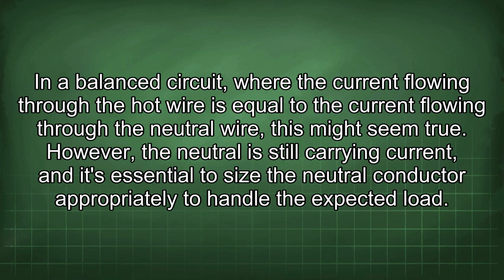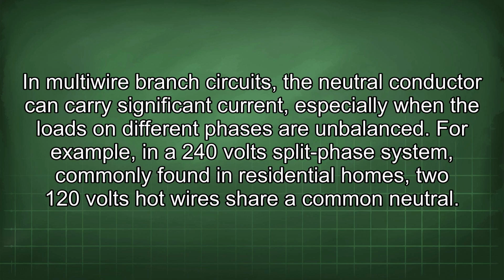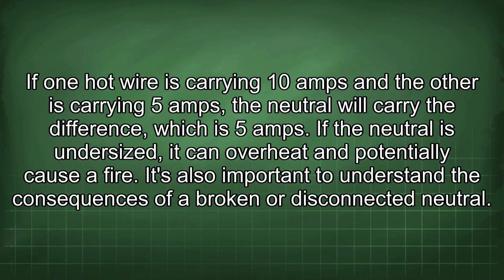However, the neutral is still carrying current, and it's essential to size the neutral conductor appropriately to handle the expected load. In multi-wire branch circuits, the neutral conductor can carry significant current, especially when the loads on different phases are unbalanced. For example, in a 240 volt split-phase system commonly found in residential homes, two 120 volt hot wires share a common neutral. If one hot wire is carrying 10 amps and the other is carrying 5 amps, the neutral will carry the difference, which is 5 amps. If the neutral is undersized, it can overheat and potentially cause a fire.